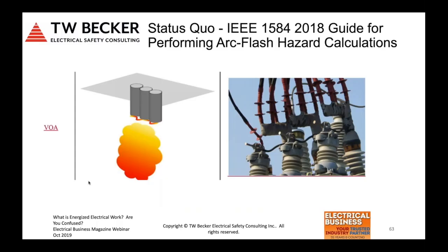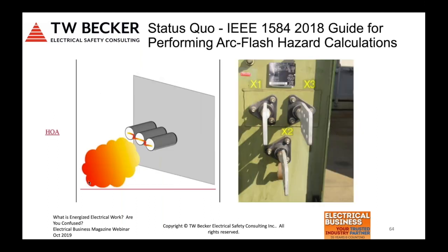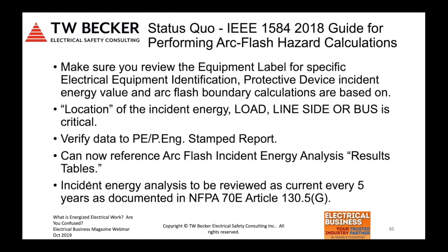And then vertical open air, again, this was previously in the 2002 edition. And then horizontal open air, again, this is a new box electrode configuration, right? So that's just quickly, unfortunately, with the time available, to introduce the new formulas. Again, the challenge here is we've got to make sure with the new IEEE 1584 that other parameters too are not conservatively assessed, or we don't spend too much attention on them. We don't have to go out to the site with a ruler or a tape measure and do measurements. We should rely on good engineering practices and the use of typical data. Again, the labels themselves, we want to make sure the label's clear for the worker, that the incident energy is on the load, line side, or bus of the protected device that's indicated on the label.